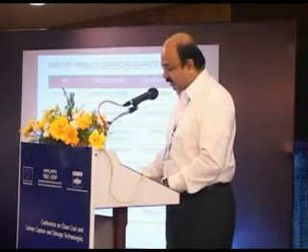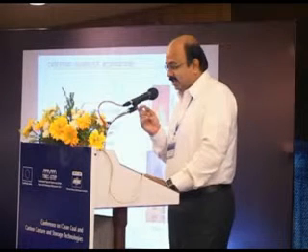Life extension, what they wanted, they were guaranteed. As part of this R&M, we have done a platen superheater upgrade. Why we do this is, as you can see in this picture if you look a little more keenly, because of the cycling it goes through, the tubes tend to move away from the center line, some to this side, some to this side. And this is the first surface the flue gas will see when it is leaving the furnace.